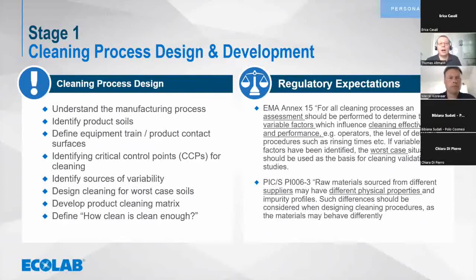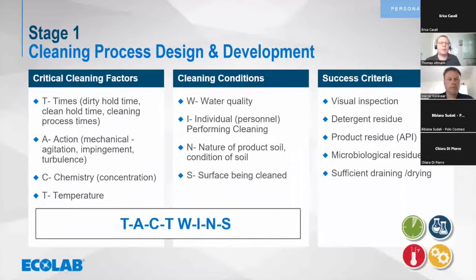The definition of how clean is clean, or how clean is clean enough, should also be made during the cleaning process design, meaning is it a 10 ppm criteria, or is it a limit setting of maximum allowable carryover?